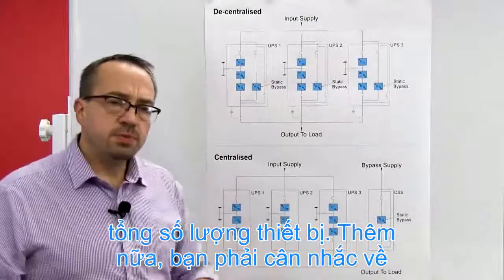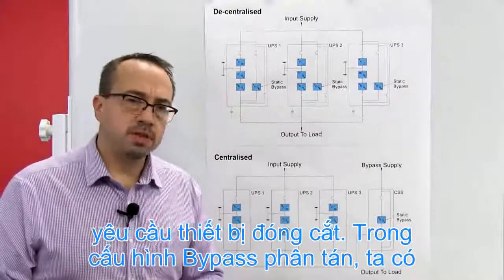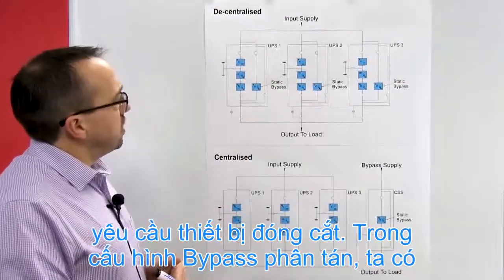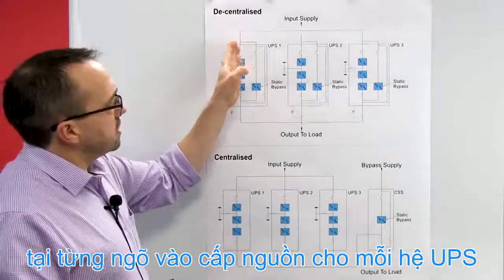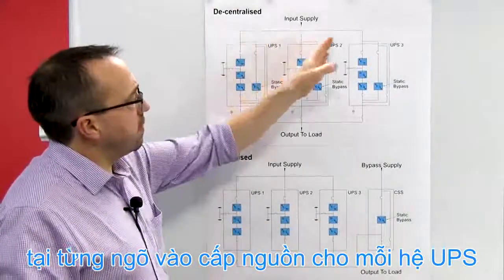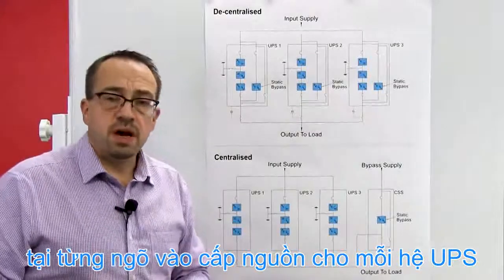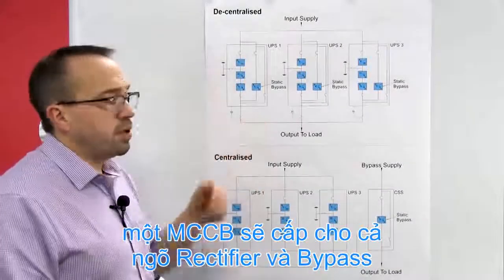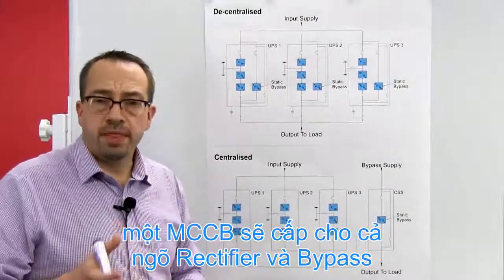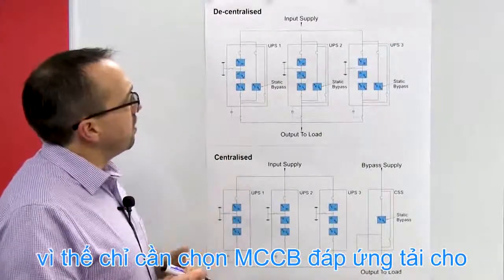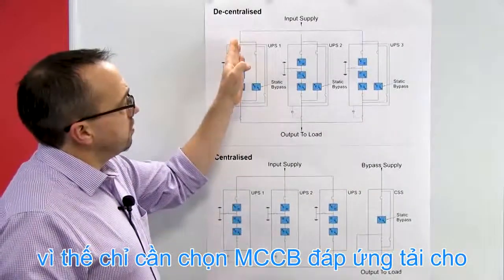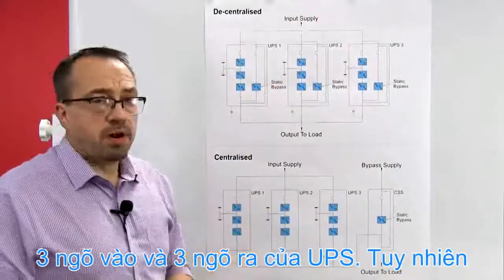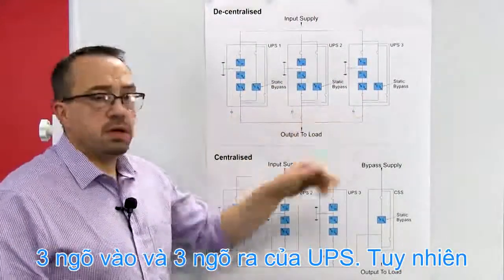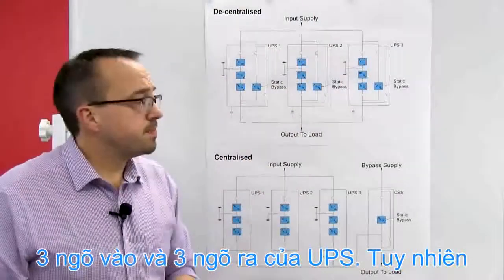In addition to this, you must consider the switchgear requirements. In the decentralized system, where we have a single supply input to each of the UPS systems, i.e. the breaker that's supplying the UPS will feed both the rectifier and the bypass line, the switchgear would only require to be fitted with 3 input supply breakers and 3 outgoing load switches.